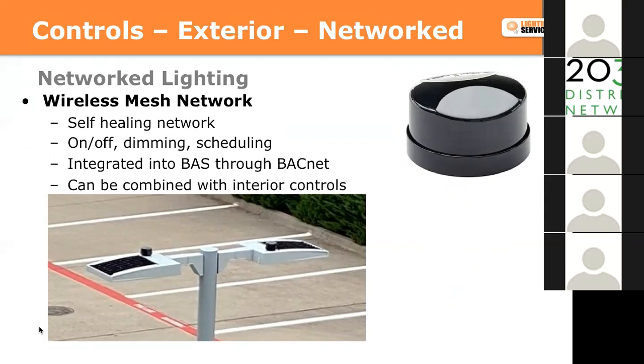The next step on exterior controls would be to network these sensors together, typically using this type of sensor, sometimes built into the fixture, but most of the time as a node you see in that top corner. You'd put these wireless nodes on all the exterior fixtures, and when commissioned correctly, they create a self-healing mesh network that ties all the fixtures together. Each fixture has its own address, and you can tie in multiple sites to one system for unified control, so if you have multiple campuses for a college or multiple buildings, it can all be tied together and controlled from one location for maintenance and/or safety and security.